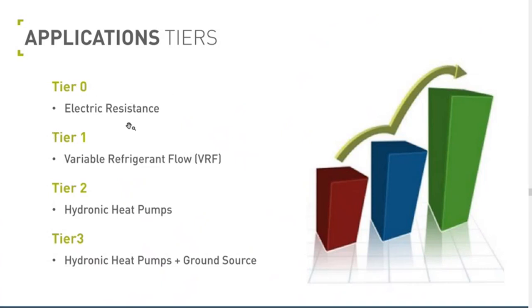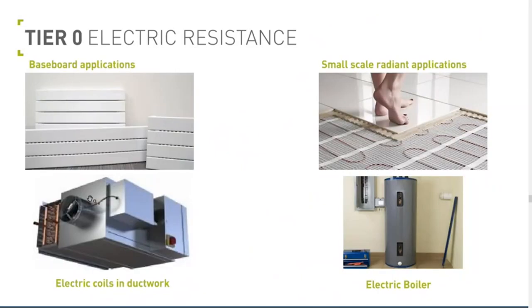From tier 0, we'll talk about electric resistance, then VRF or air heat pump technology, then hydronic heat pumps - an air-to-water heat pump that extracts heat from the atmosphere or air, generates hot water, and pushes that through a building or to domestic hot water systems. Tier 3, the last one, is a ground source system using geothermal energy - energy within the earth. The temperature of the earth is a lot more stable and constant through our lifetimes and the planet's existence than outside air temperature, so using the ground to extract heat is a lot more efficient. We'll talk about those efficiency differences.